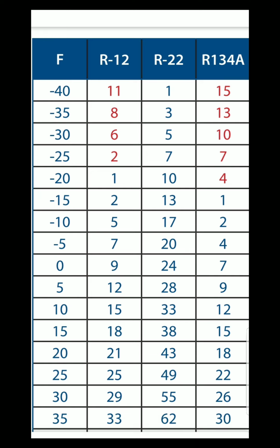Okay, so here's the PT chart for R134A on the right side, and at the bottom we see 30 psig. It corresponds to 35 Fahrenheit saturation temperature.